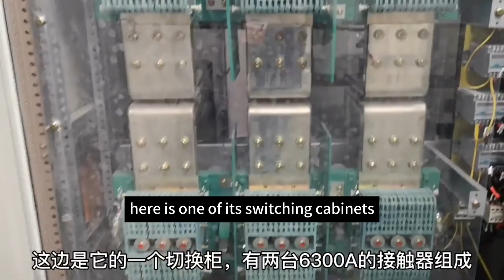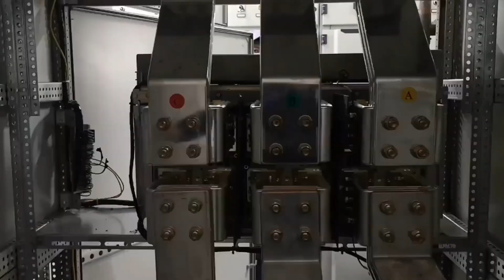Today, let's take a look at the 6300 ampere cabinet. Here is one of its switching cabinets, consisting of two 6300 ampere contactors. Let's look at the copper bar behind the circuit breaker here. Each item consists of 3 bronze bars of 12 by 125.